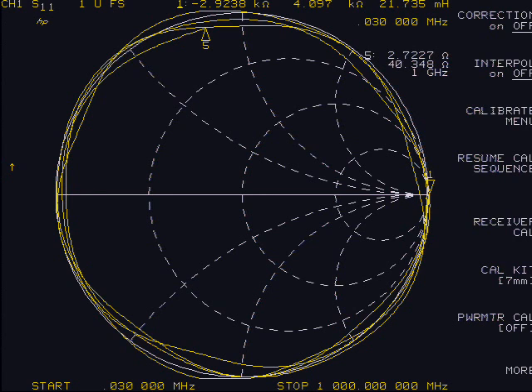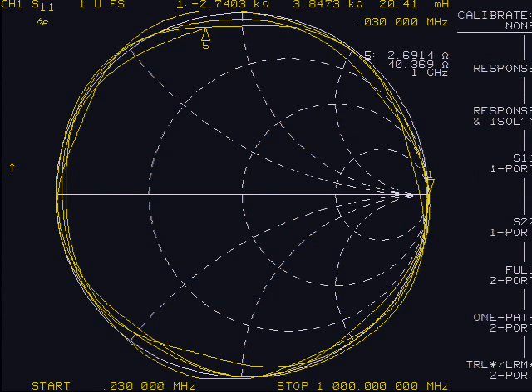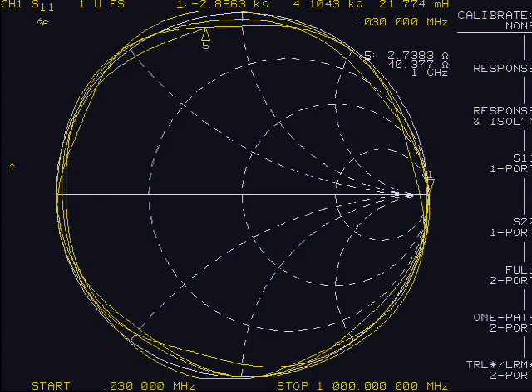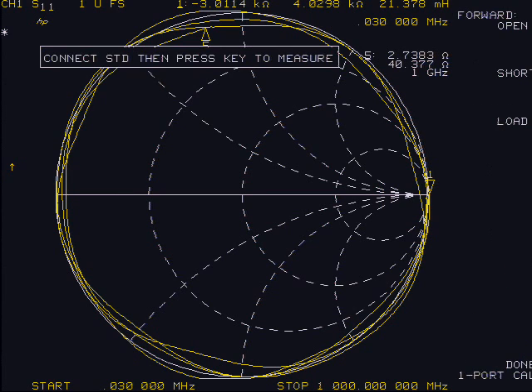Calibrate the unit by selecting the Cal button, then calibrate menu soft key, then S11 1-port soft key.